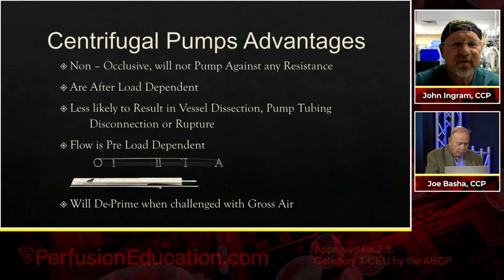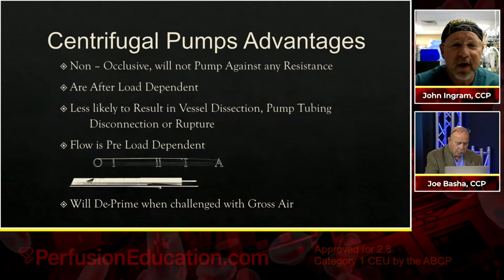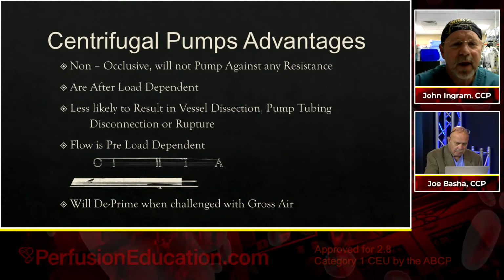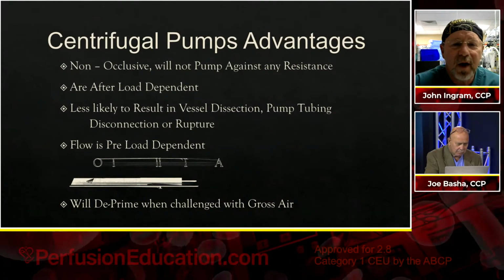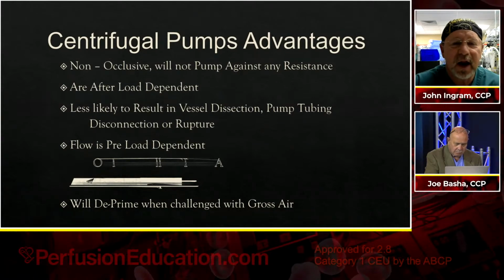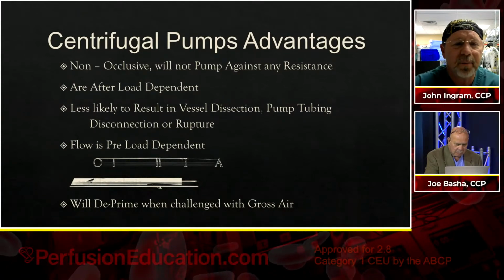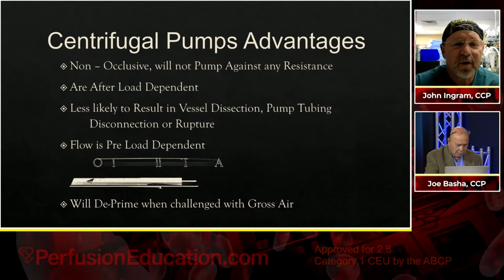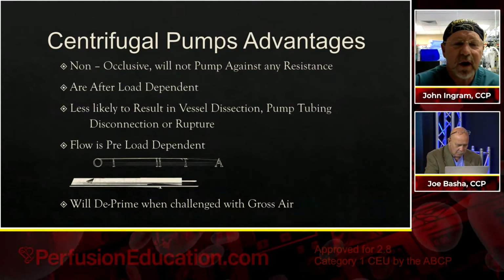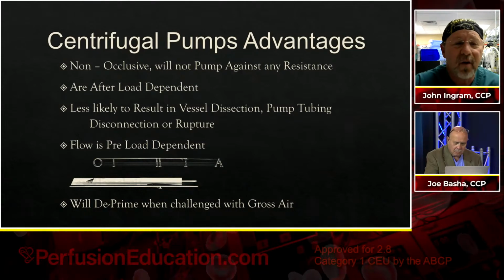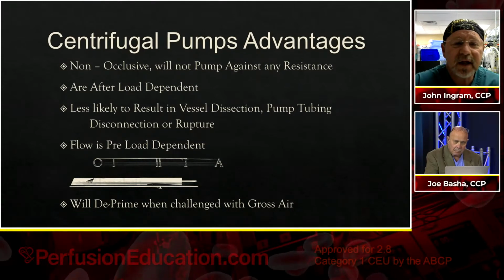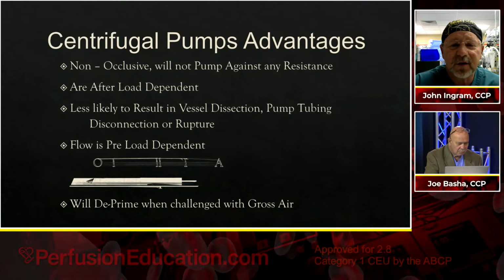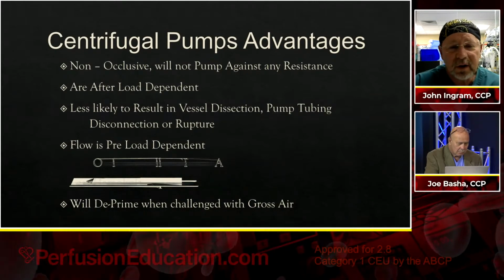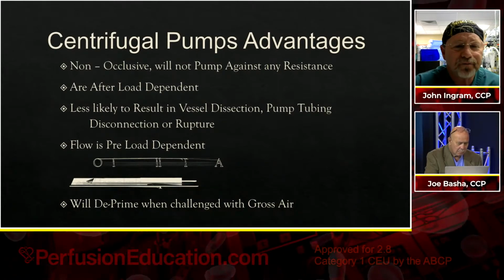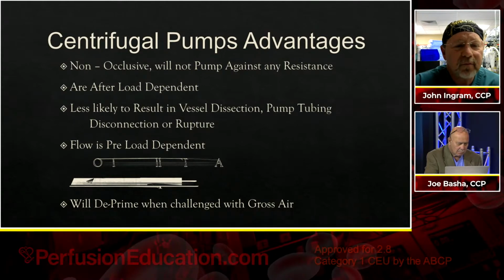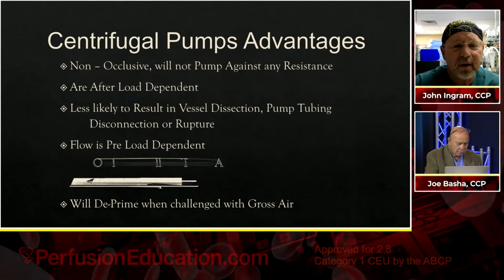So some of the advantages of centrifugal pumps. It's non-occlusive, so it will not pump against any resistance. At a certain resistance, it will no longer continue to pump. It is afterload dependent. You have too high of an afterload, it'll pump either less or nothing at all. It's less likely then to result in vessel dissection, pump tubing disconnection or rupture. That's different than the roller pump model. And the pump is preload dependent.